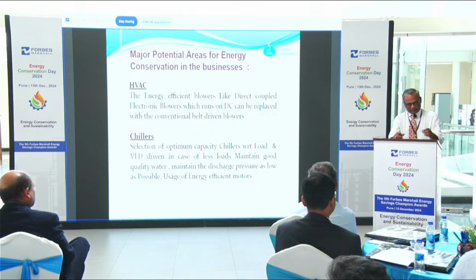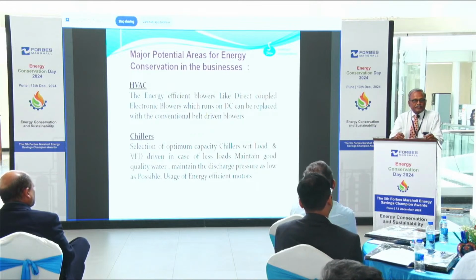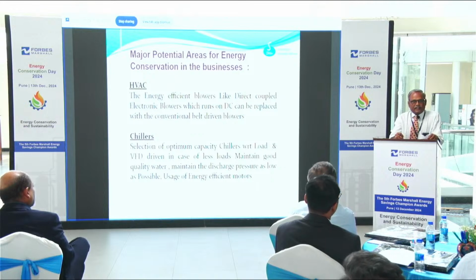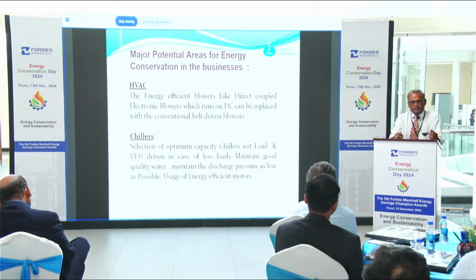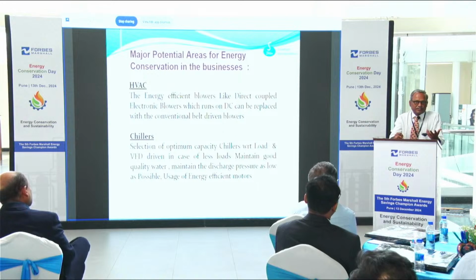Regarding chillers, if load variations are there, we can go for VFD driven chillers. When it comes to monitoring parameters like discharge pressure and suction pressure, wherever we maintain the discharge pressure as low as possible, the per-TR kilowatt consumption will be very less. You can achieve good results in that.